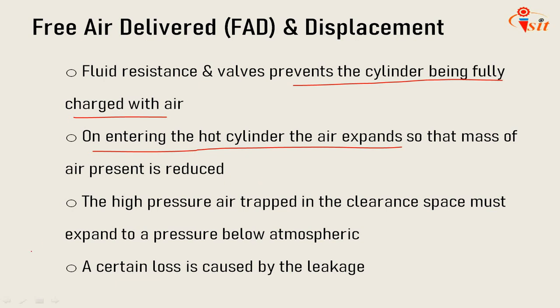Now third one is the high pressure air trapped in the clearance space must expand to a pressure below atmospheric before the automatic suction valves can open. A portion of the suction stroke is therefore wasted in effecting this expansion.